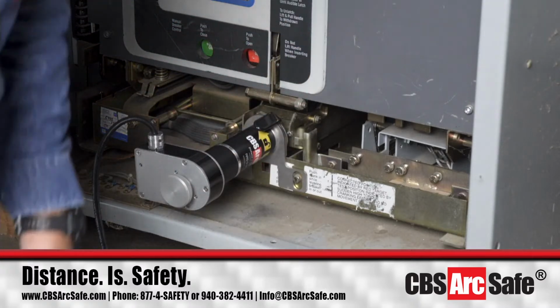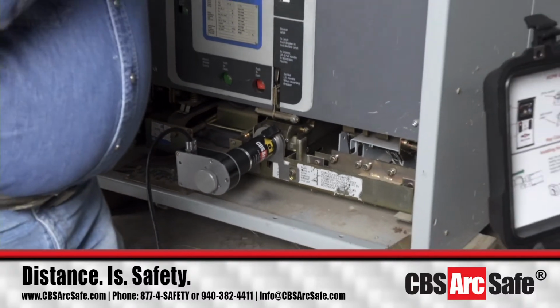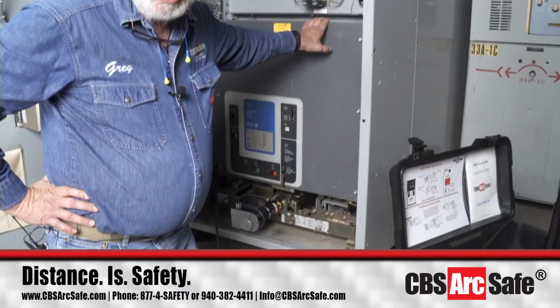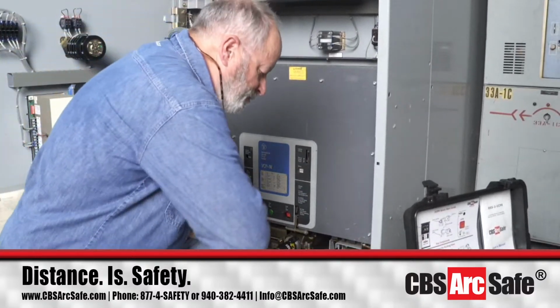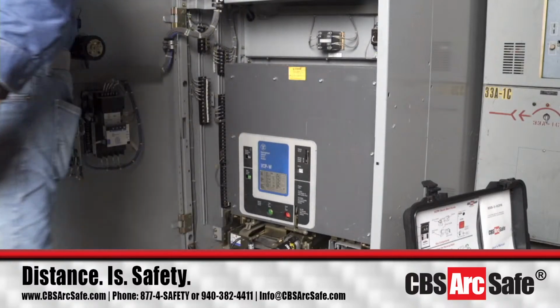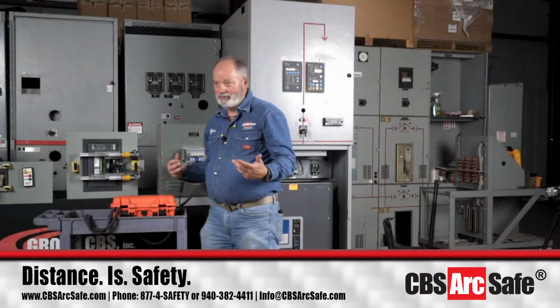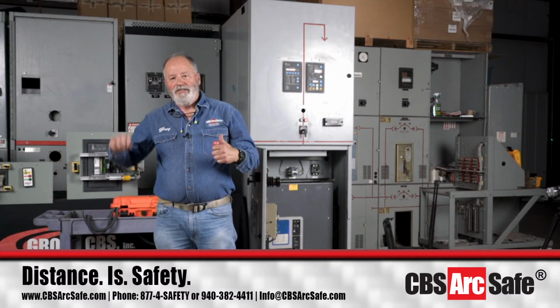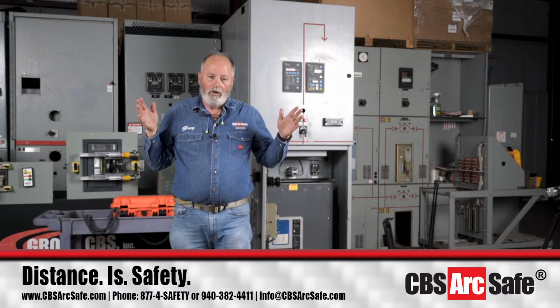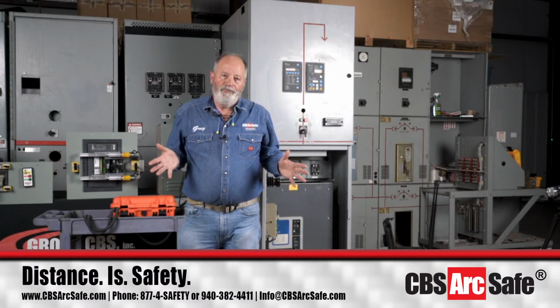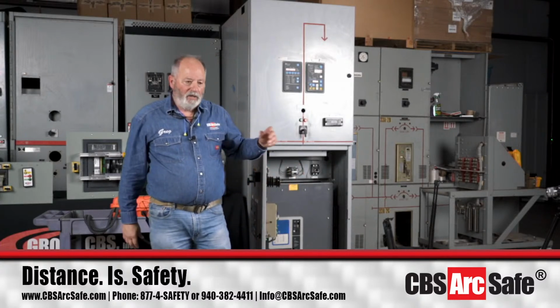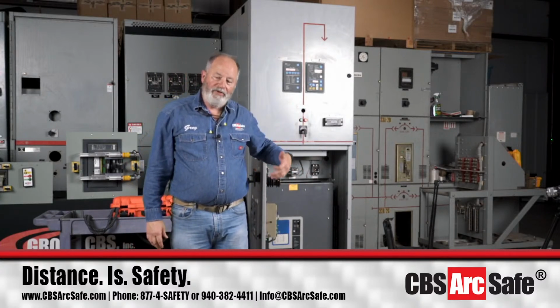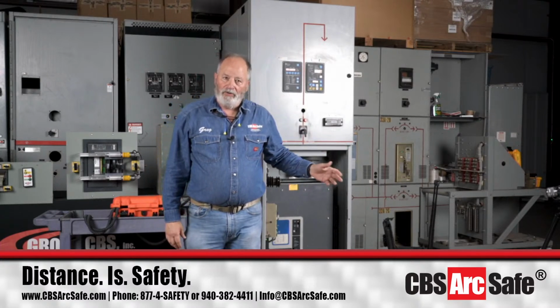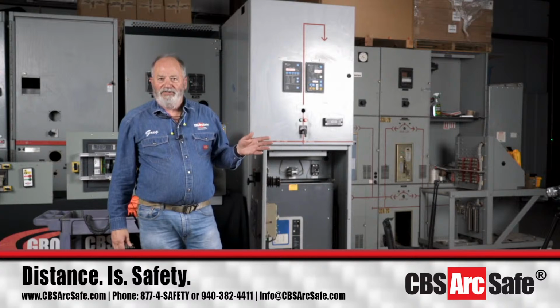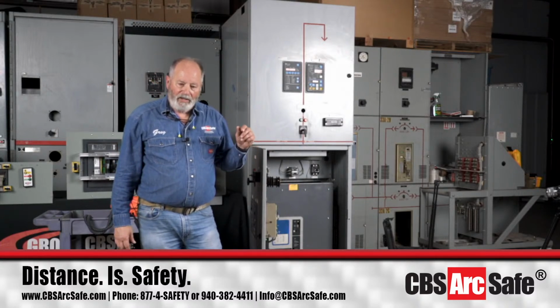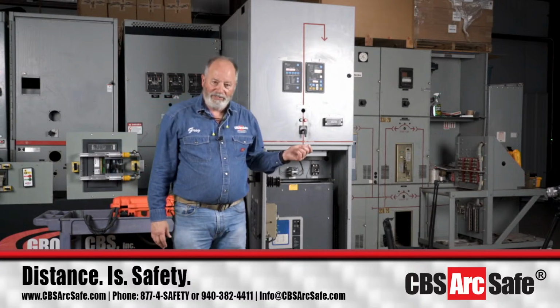Okay? Now, every once in a while, you'll find a breaker or a cubicle, whether it's in a VCPW or in a power vac, that things aren't right. Just to talk about the condition of the switchgear: remote racking doesn't repair the damage or manufacturing defects in switchgear. And the reason I say that is this: most of your VCPW breakers, from 1200 to 2000 to 3000 amp breakers, are going to rack with under about 15 to 17 foot-pounds. The 1200 and the 2000 amp are usually going to rack with under about 13 foot-pounds of force.